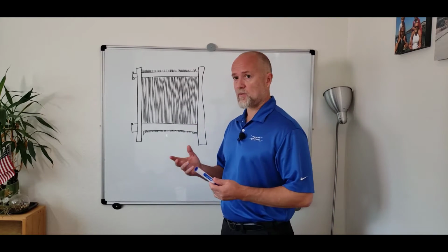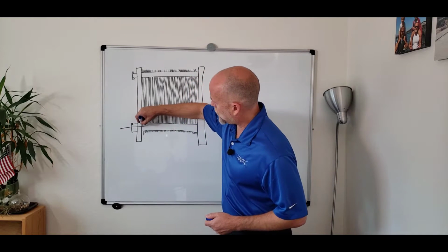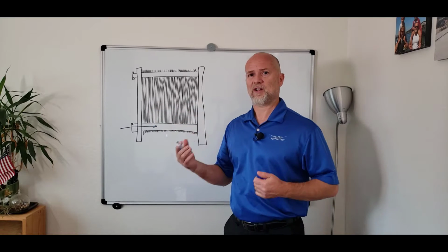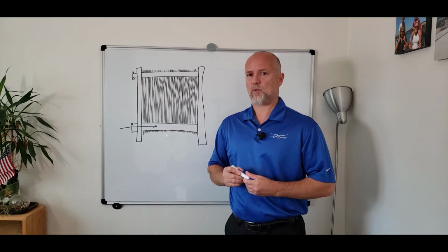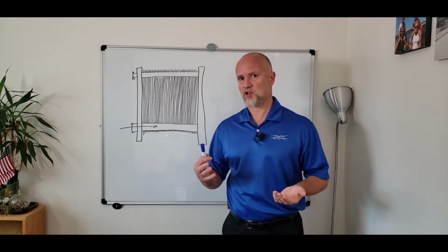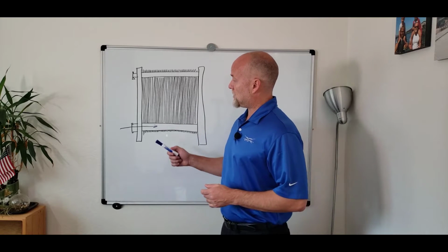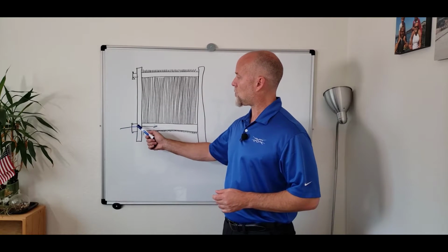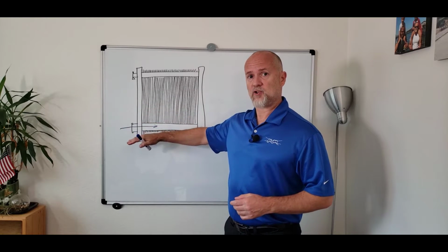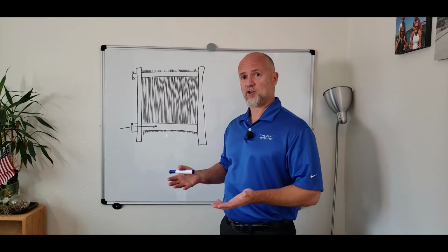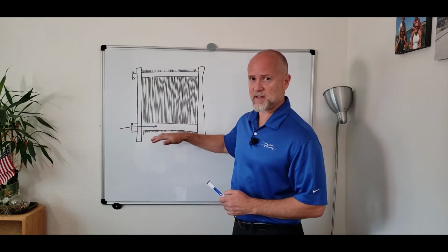Well, first of all, imagine this is the inlet, let's say the cold inlet, which normally is the more challenging because it comes from the cooling tower, so you might have debris, you can have fouling issues. So the cold inlet normally is the most challenging one. And that's the reason why we suggest to always put it at the bottom of the heat exchanger and not at the top, so you can take advantage of the positive pressure coming from the pump. So you imagine that this is the inlet.